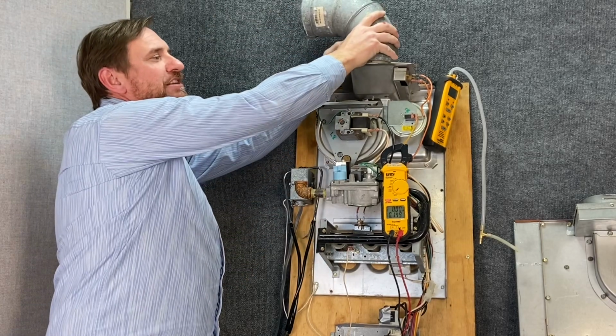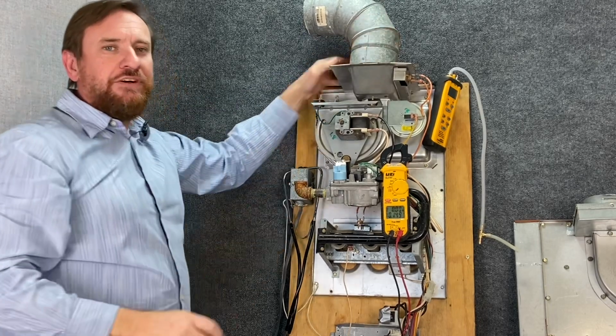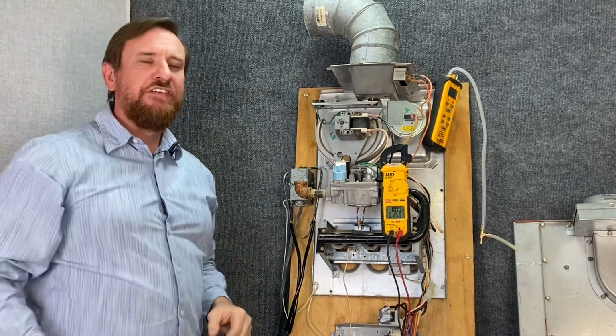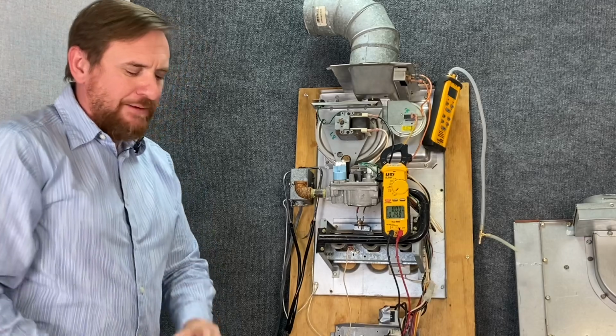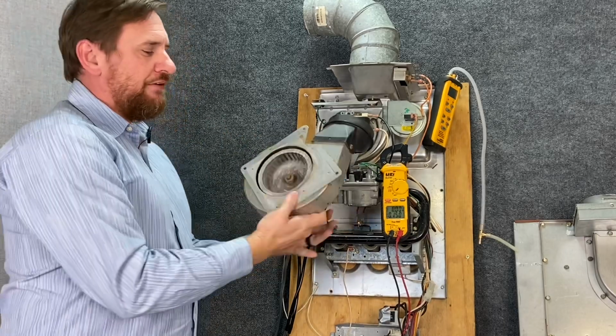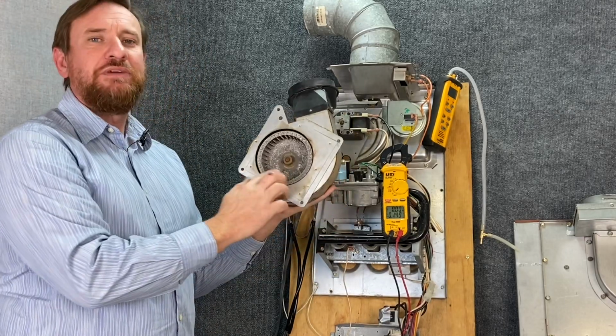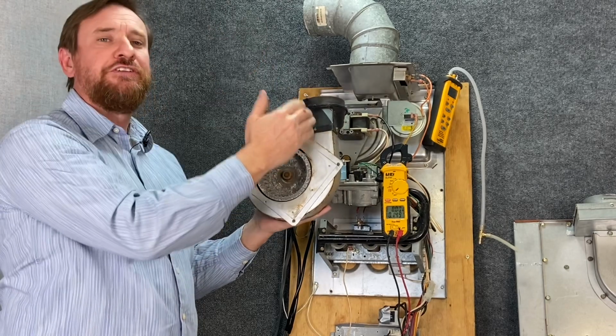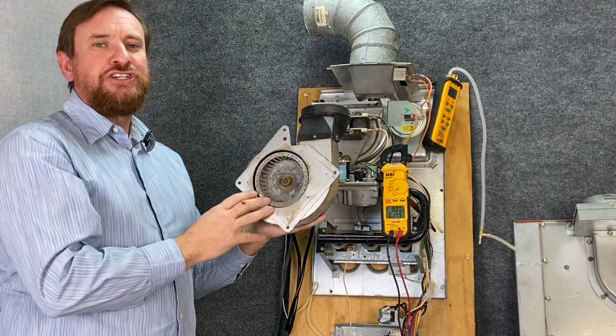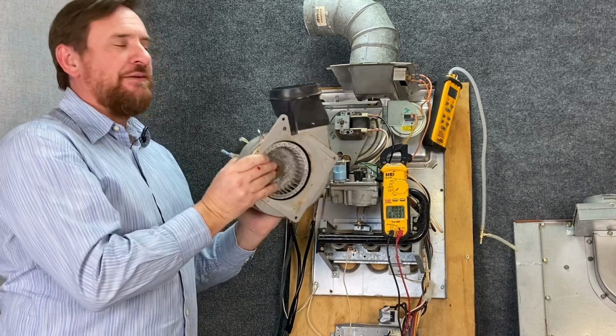So knowing the condition of that inducer wheel is going to tell us a lot about the condition of this heat exchanger. For example, this wheel, we have a significant amount of corrosion. So we have some kind of a moisture issue, either coming from the flue pipe or improper combustion in that heat exchanger. So these are some very important things.